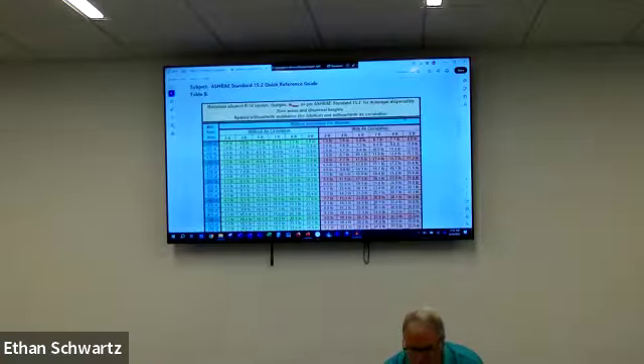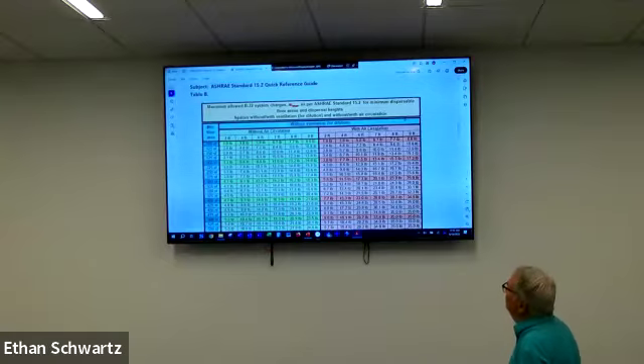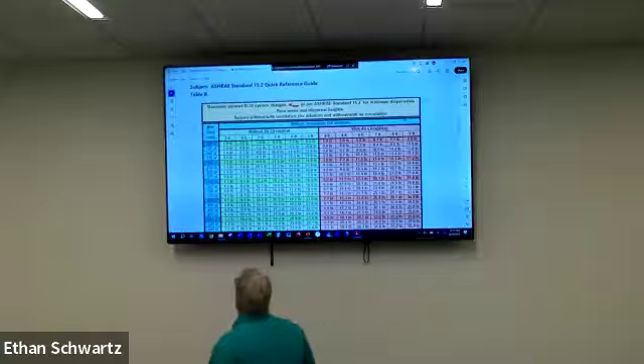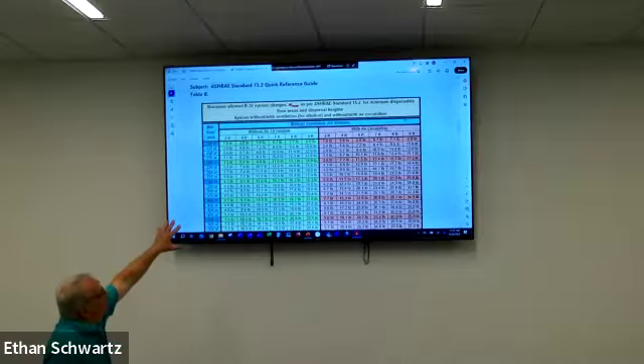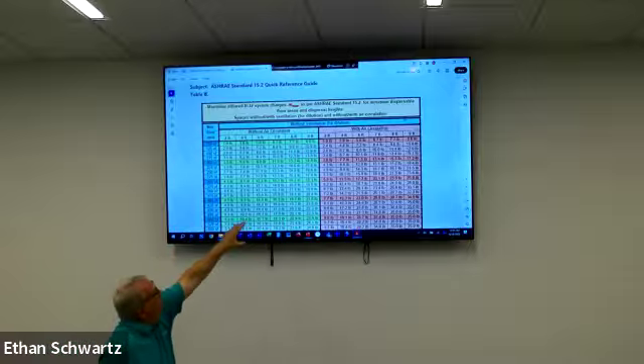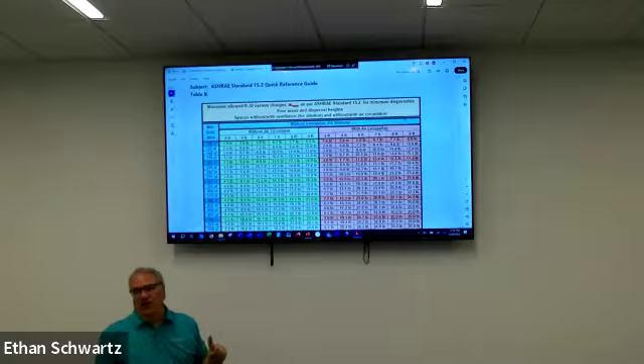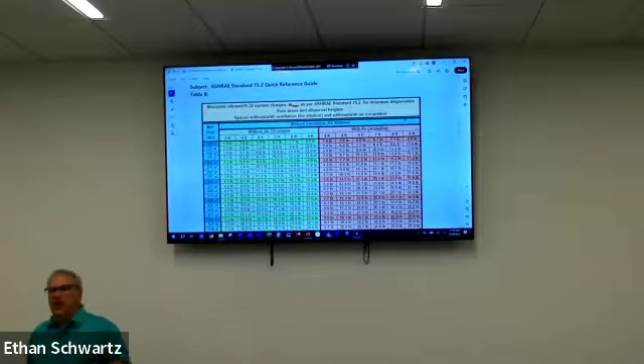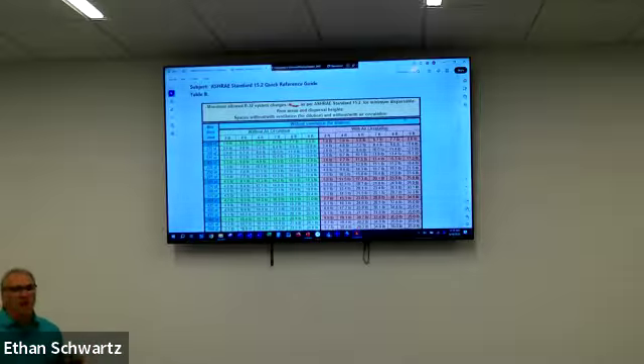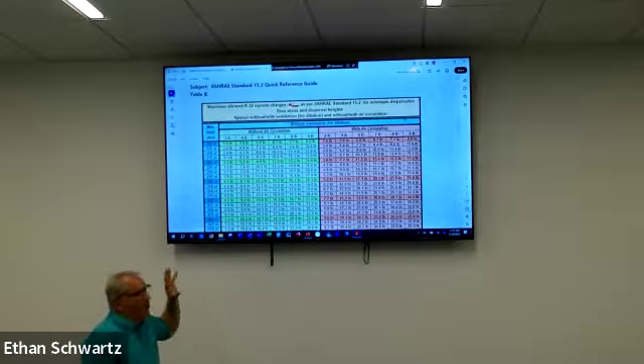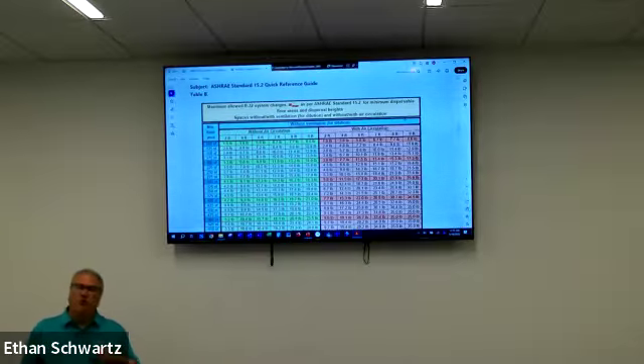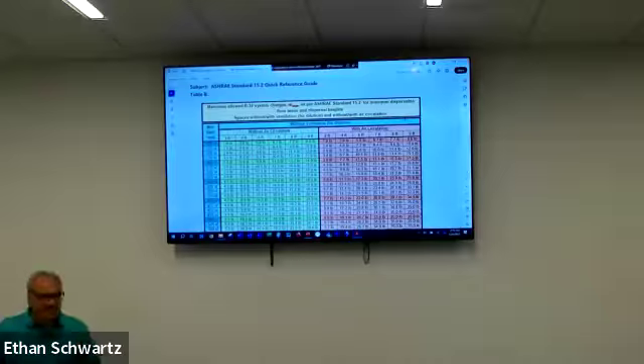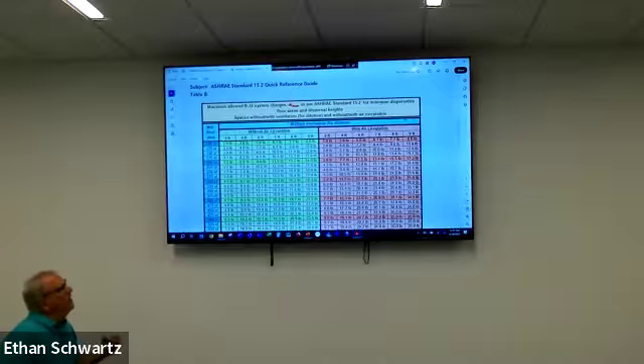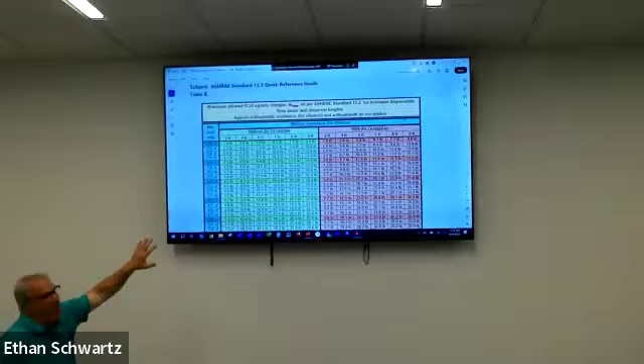And then it also, and this is something that I think Kevin's going to mention to you, there's a couple ways to figure this, but let's just look at this table just so you know what you're reading. And that is without air circulation and with air circulation and without ventilation. So Johnstone here, I know, is selling ERVs, HRVs. Those are common in homes, things like that. So when you're transitioning to the R32, the contractors are going to have to be aware that they get some credit for the size of the refrigerant, or the amount of the refrigerant, based on the size of the system if they have ventilation.